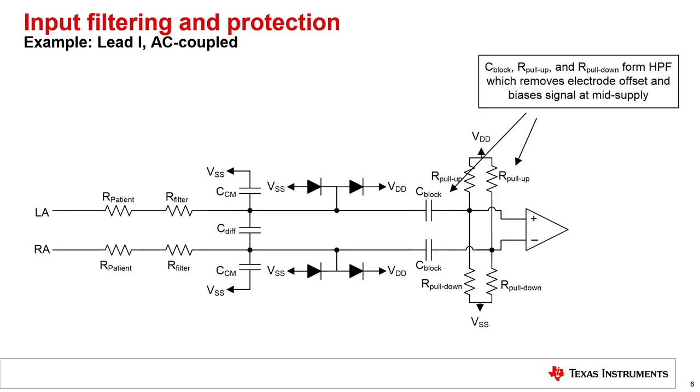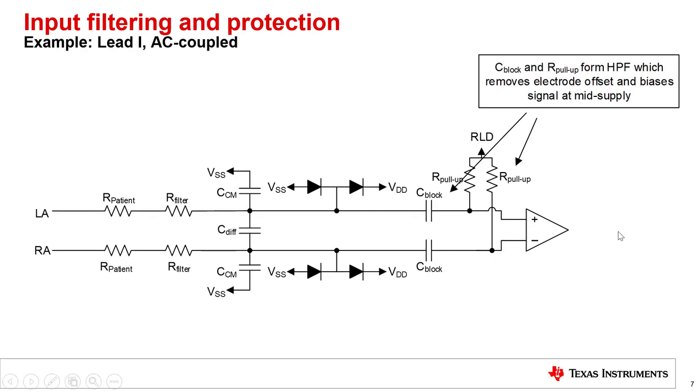Some applications may prefer to not use the RLD electrode in order to reduce the number of connections and to save on cost. In this case, the input to the INA will need to be AC coupled using the series capacitors C block. The input signal path will still look very similar to the DC coupled version. The exception is that a resistor divider between the supply rails is needed to set the DC common mode voltage, typically to mid-supply. Alternatively, a single pull-up resistor to an available mid-supply rail can also be used. The combination of these resistors and C block form a high-pass filter that will block the floating bias voltage of the body. The cutoff frequency for the high-pass filters can be as low as 0.05 hertz while providing the ECG signal content.